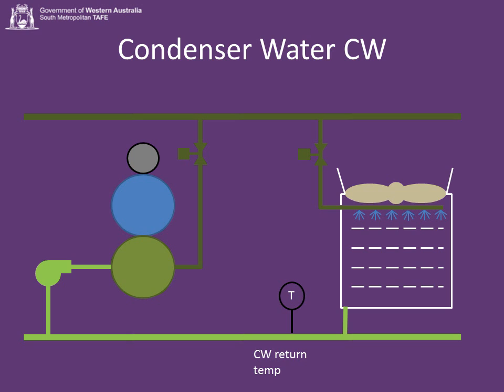We run the fan on that cooling tower using a VSD, so that we maintain a condenser water leaving the cooling tower, a pond temperature, and that is the condenser water return temperature to the chiller. Okay, so we maintain that so that I think we're maintaining it sort of 30 odd degrees Celsius, condenser water coming back, maybe 25 if we can get it. There's a whole video on cooling towers where we talk about the cooling tower, its approach, its efficiency, its range, and that sort of thing.